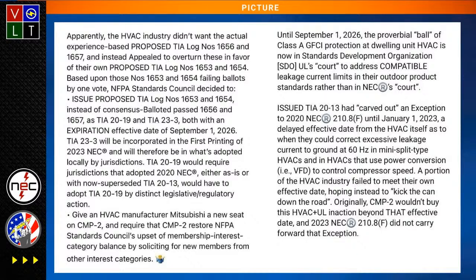Did they explain the difference where you have an A, B, C, D, and E? I've already argued that with our little friend that hates me now. But the whole thing is that a Class A has to be a Class A. A GFPE can dial down to 6 milliamps, but that doesn't comply with the code language. Now with special purpose GFCI, you can do that.